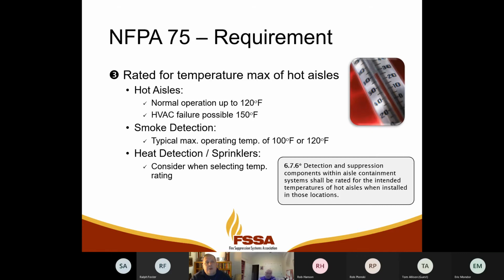So it can no longer does a data center have to be as cold as a meat locker for energy efficiency. The equipment can withstand those higher temperatures, which on the hot aisle side is raising the temperature up and giving us a problem with our conventional equipment. And then sprinklers. Most data centers have ordinary, quick response sprinklers with temperature ranges of 135 degrees.